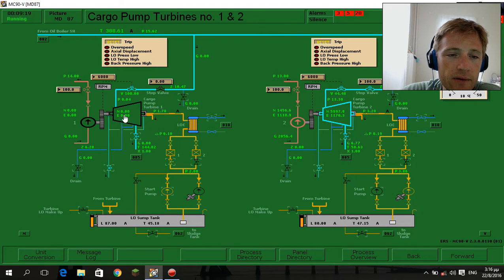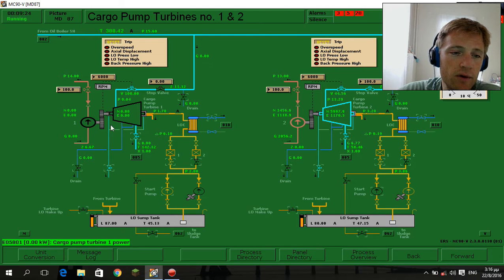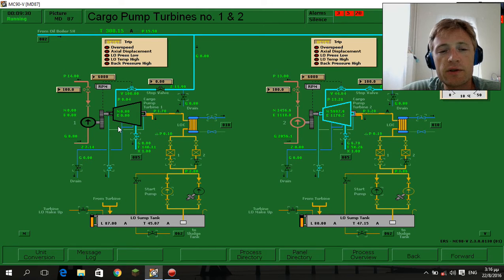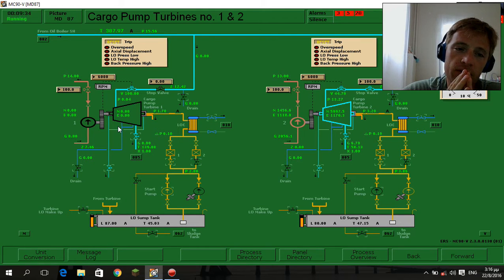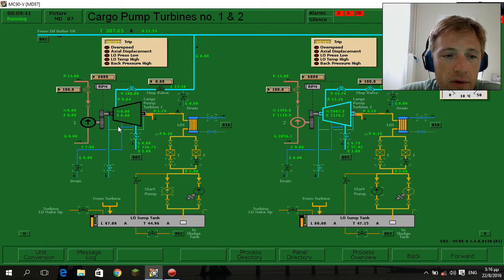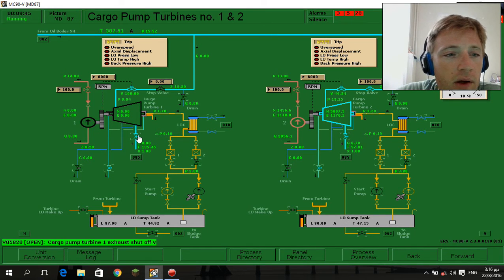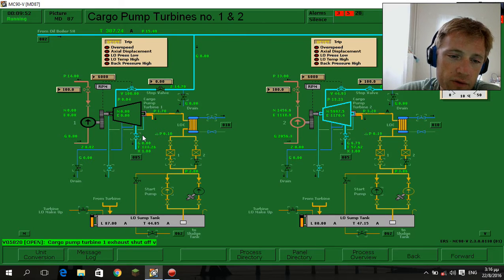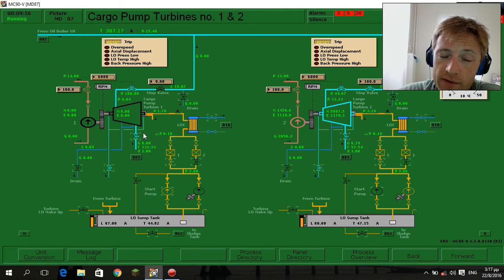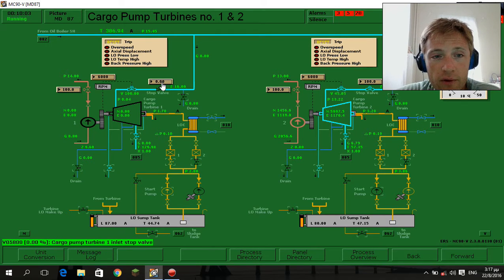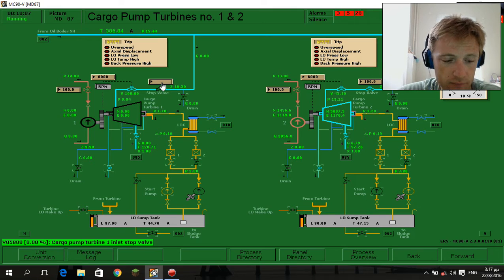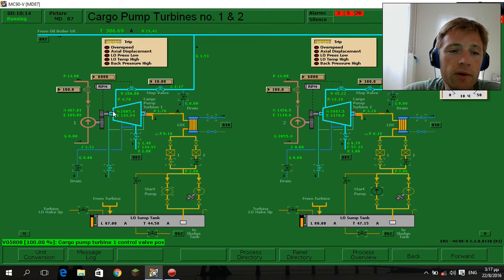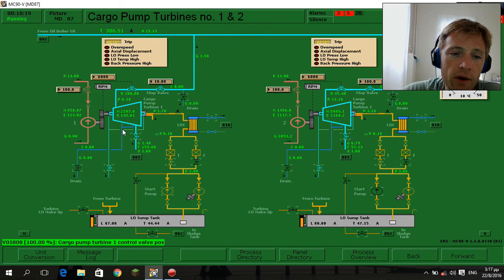The gland steam going here, this is the gland steam going here to this place. The gland steam - the main purpose is there is some labyrinth inside - is to seal the turbine steam, to not pass through the shaft and go outside. Let's talk about how to start the pump. The most better way to start the pump is to start slowly. With this we achieve a smooth start. Let's set to 10, 10 percent. Also your pump will slowly heat all the components, and the temperature is easy to increase.